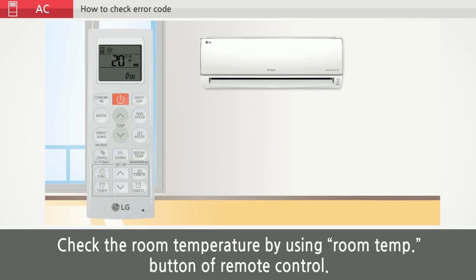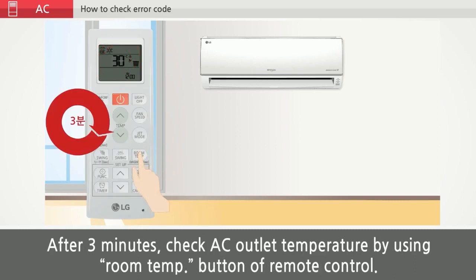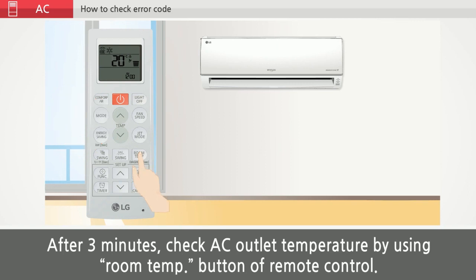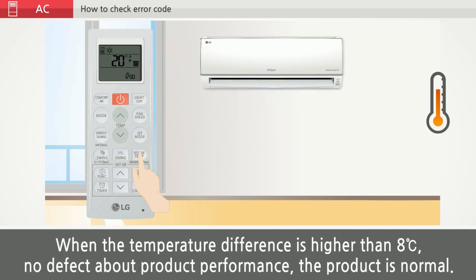Check the room temperature by using the room temp button on the remote control. After 3 minutes, check the AC outlet temperature using the room temp button on the remote control. When the temperature difference is higher than 8 degrees Celsius, there is no defect about product performance — the product is normal.